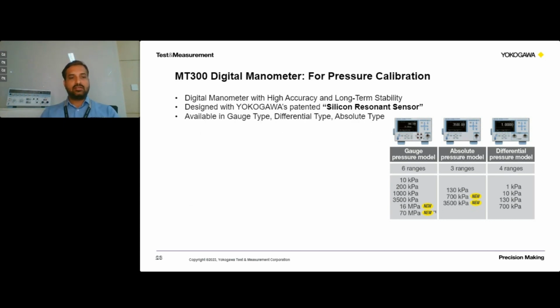In this, we have got a gauge type, differential type, and absolute type. In gauge type, we have got 6 ranges starting from 10 kilopascal to 70 megapascal. In absolute ranges, we have got 130 kPa to 3500 kPa. 3 ranges we have. We also have got a differential pressure manometer to cover the calibration of differential pressure transmitters and the devices which work on differential pressure. So we have got 4 ranges starting from 1 kPa to 700 kPa.